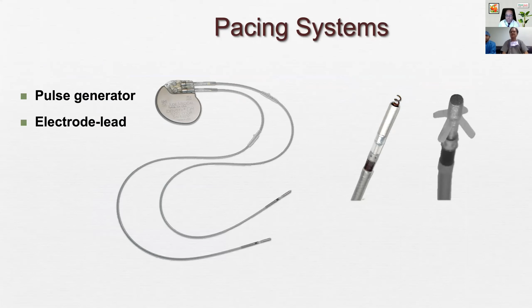Along the way, some common standards were developed, and the most important ones were related to the lead, so that each manufacturer's leads became compatible with the other manufacturers. In this regard, a very important development is called the IS-1 standard for leads. And then we have the IS-4 standard for quadripolar, and DF-4 for the defibrillator leads. But for the pacemakers, a vast majority have this IS-1 standard, so that every manufacturer's lead is compatible with other manufacturers' leads.